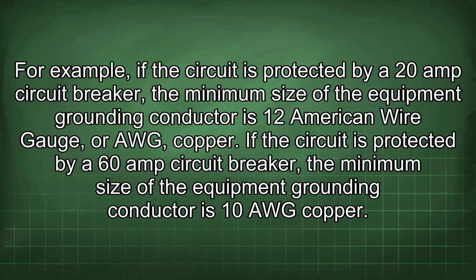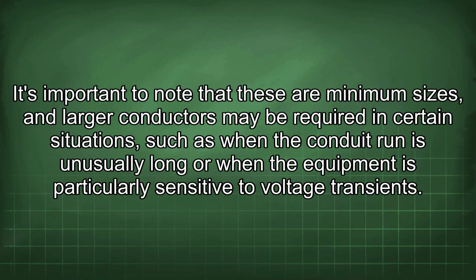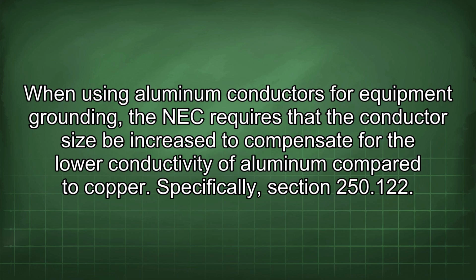If the circuit is protected by a 60 amp circuit breaker, the minimum size of the equipment grounding conductor is 10 AWG copper. It's important to note that these are minimum sizes, and larger conductors may be required in certain situations, such as when the conduit run is unusually long or when the equipment is particularly sensitive to voltage transients. When using aluminum conductors for equipment grounding, the NEC requires that the conductor size be increased to compensate for the lower conductivity of aluminum compared to copper.